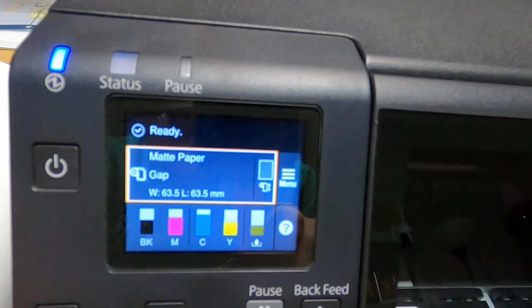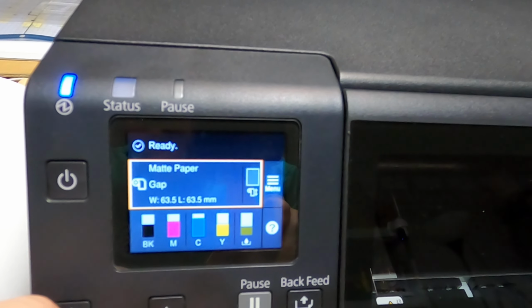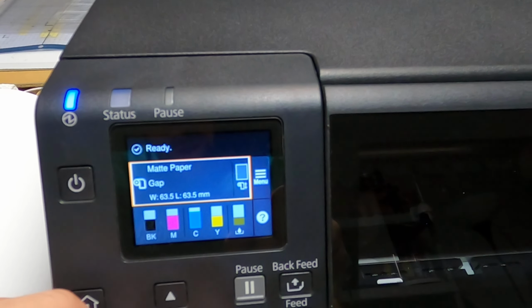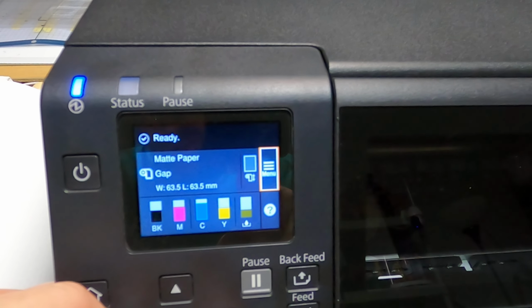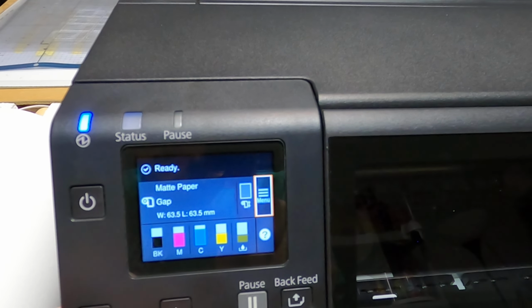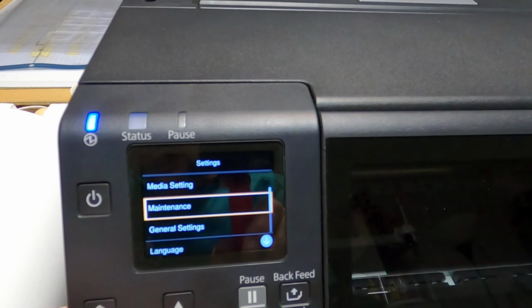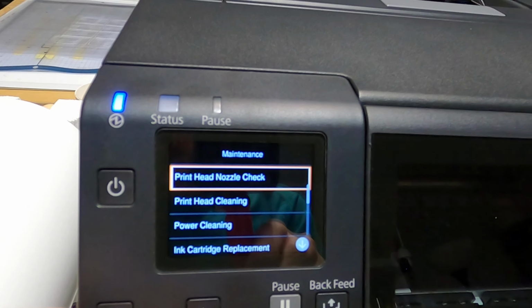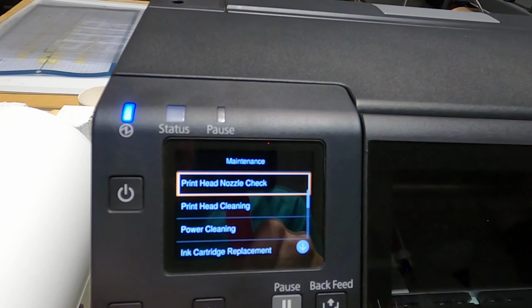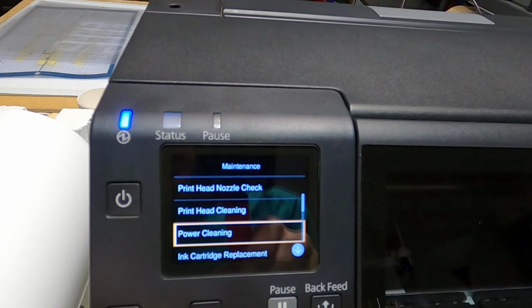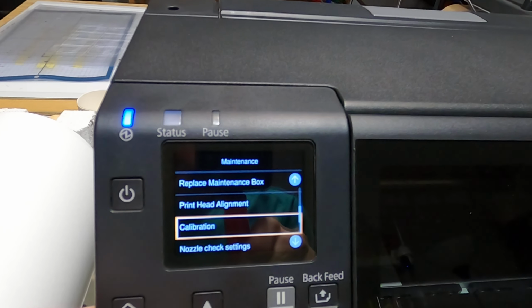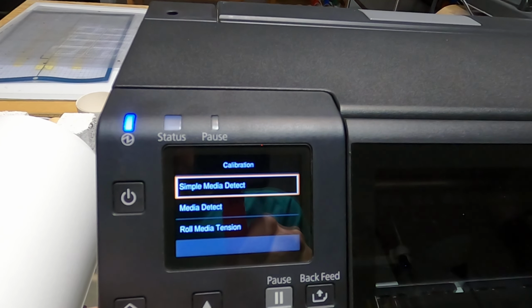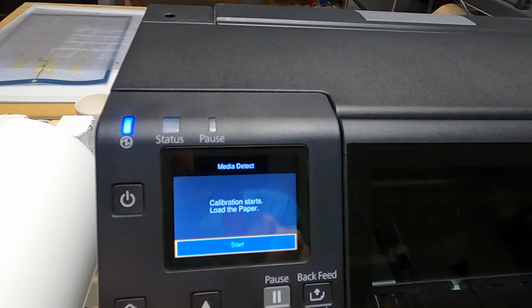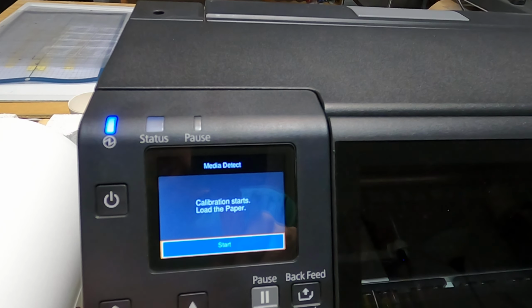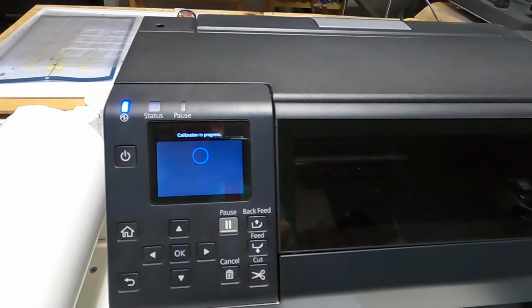But what you're going to want to do here is click on. You're going to want to scroll this over to where it says menu. You're going to go down where it says maintenance. It's the next one down. I'm sorry if this isn't in focus. You're going to go down to where it says calibration. And then you're going to go media detect. And you're going to go select or start, and then you're going to hear it say calibration in process. It's going to start doing its thing.